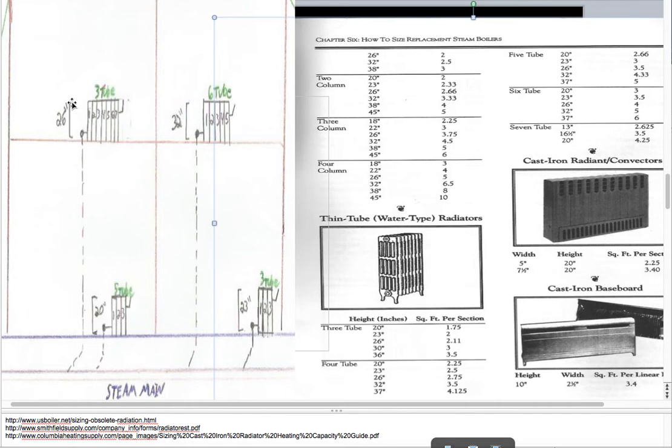So this first radiator here is 26 inches tall and it's a three tube. So there's your tubes going along this way from the front or the back, depending on where you're looking at it. It's 26 inches tall. Here's your height right there. Three tubes. You get 2.11 per section, we have one, two, three, four, five, six, seven sections.